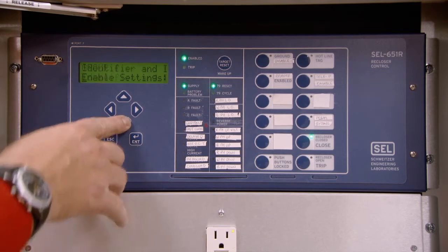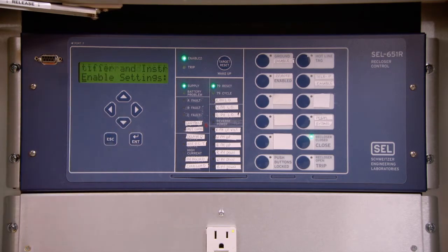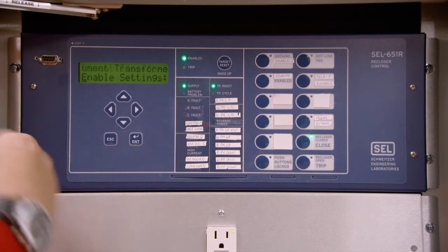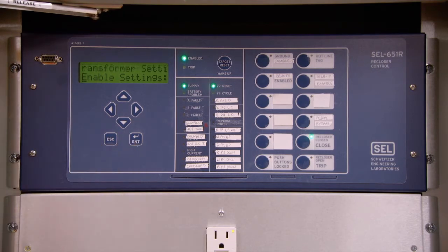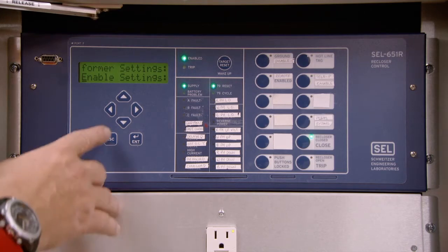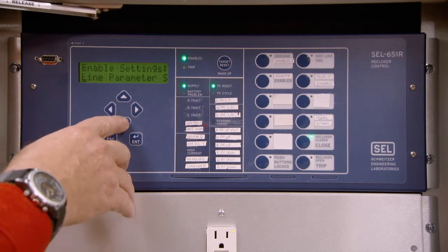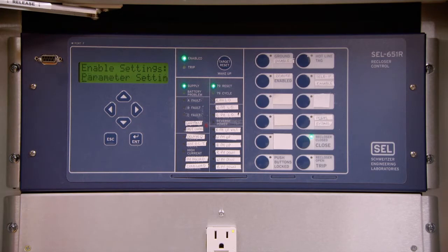Press the down arrow. You may now enable those settings by pressing Enter. Any changed settings may be saved. Press the down arrow to select Line Parameter Settings. This feature allows you to set the qualifications for the distance to fault, etc. These functions would be set from a laptop by P&C staff.